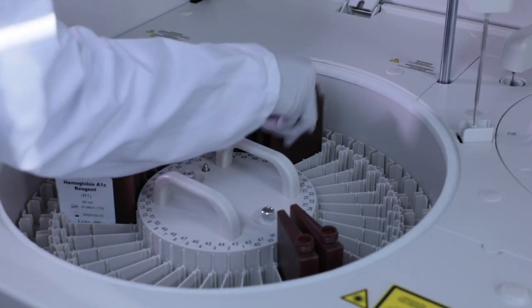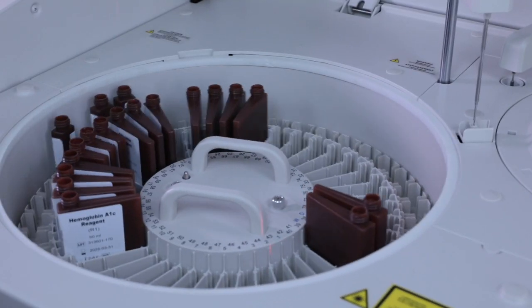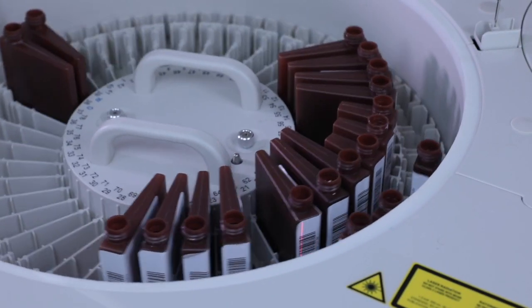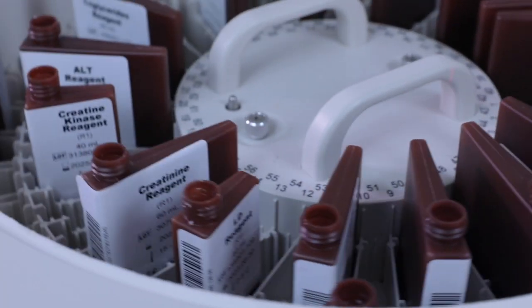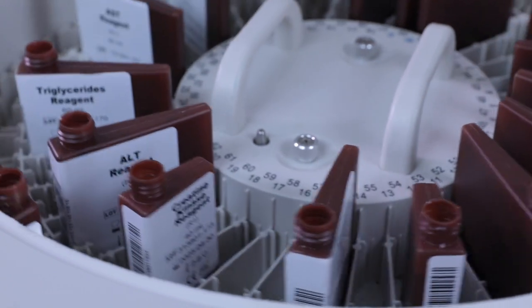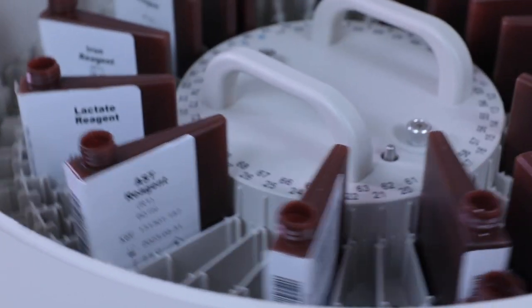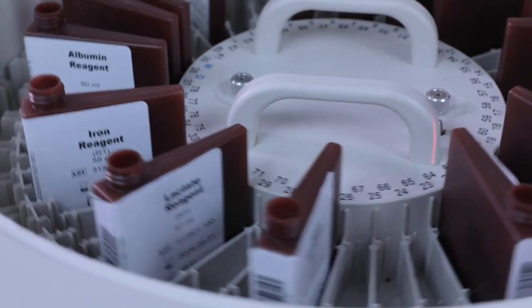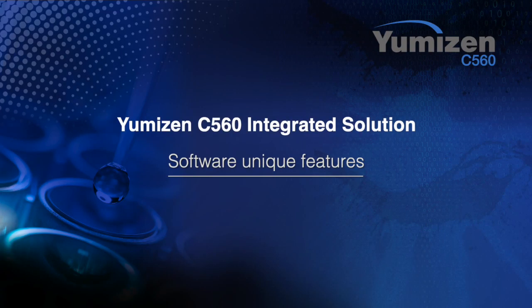The Yumizen C560 solution offers a comprehensive panel of tests — 41 tests with pre-installed validated methods with Oriva Point barcoded reagents. The reagent carousel can store up to 80 cassettes and provides 24-hour non-stop cooling at 2–10 degrees Celsius.